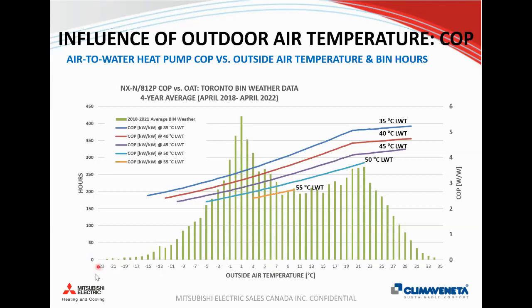Yes, our design temperature in Toronto for the building codes is around -23, but you'll see these extreme cold days have a relatively low frequency. Really, for most applications of these types of heat pumps, you'll use them down as cold as -10, maybe -5, and as high as about 10 into the shoulder season. Even so, between -10 and +10 for Toronto, we spend over 50% of the year. So I always refer to that as good heat pump weather.